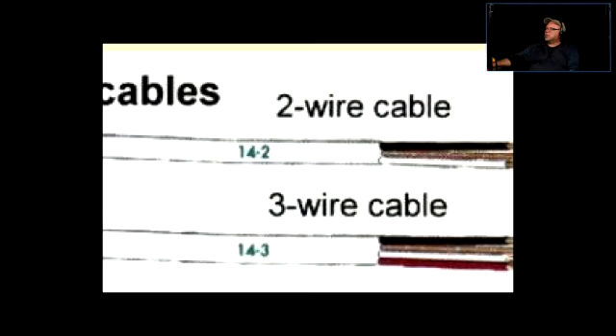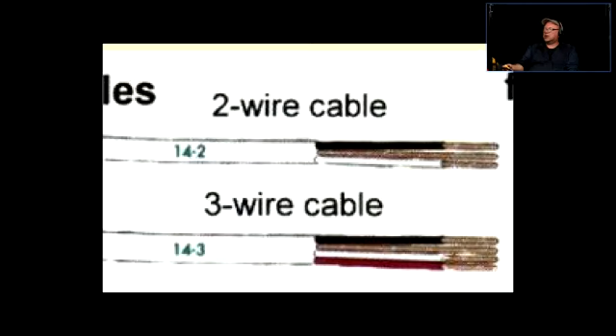Now why is it that we see 3 conductors here and we are calling it a 2-wire cable? There's a cable - that's the whole system of wires enclosed in a sheathing. And we see 3, but we call it a 2. Well, we're considering as 2 based on a concept called current carrying conductors and other safety, non-current carrying conductors.